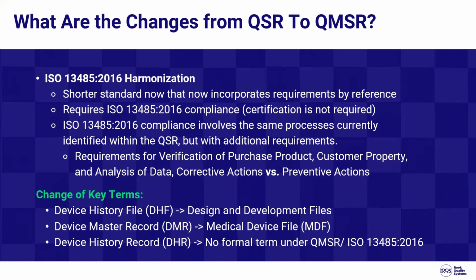So under the QSR and under FDA as it stands today, CAPAs are a single process for corrective and preventive actions, while under ISO, they are two separate things, corrective actions and preventive actions. A couple other key terms are going to be changing. So device history file, that's a term that's found in 21 CFR today. The ISO term for that is design and development file, so just a semantics change there.